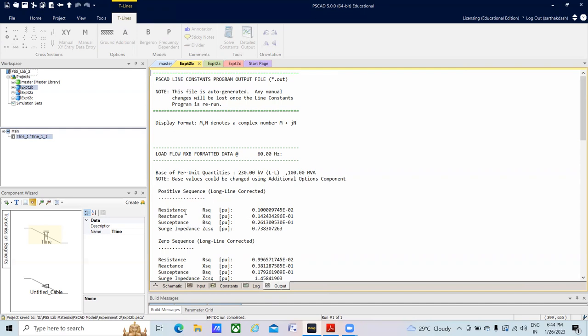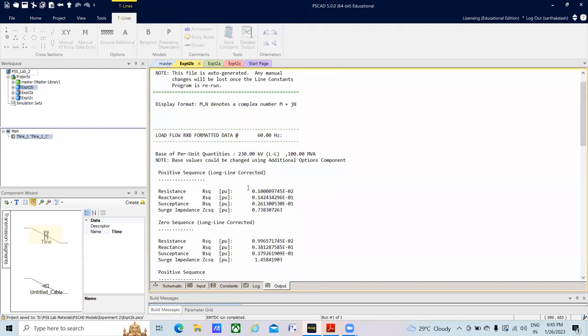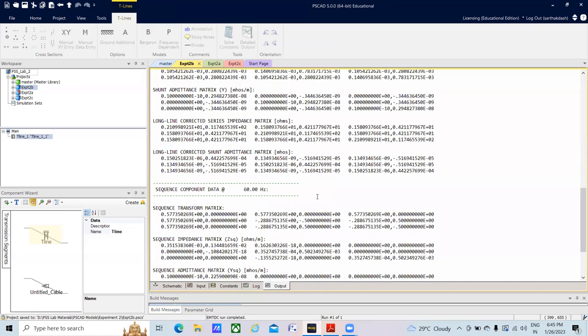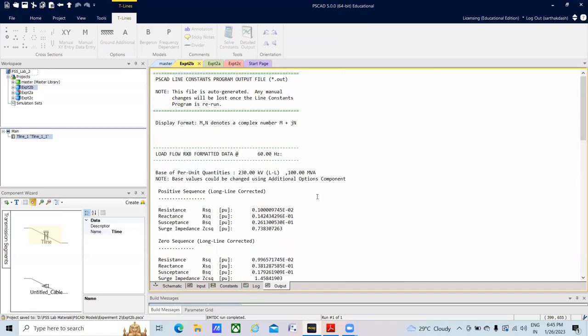Go to the output section and you can see the parameters in RXB format at 60 Hz. Resistance is around 0.001 per unit — everything is in per unit. You can also see positive-sequence resistance and reactance as well as zero-sequence reactance. There are also matrices available to explore. The resistance value is in series with the reactance, and adding these gives the impedance matrix. There is also a shunt admittance matrix to explore.